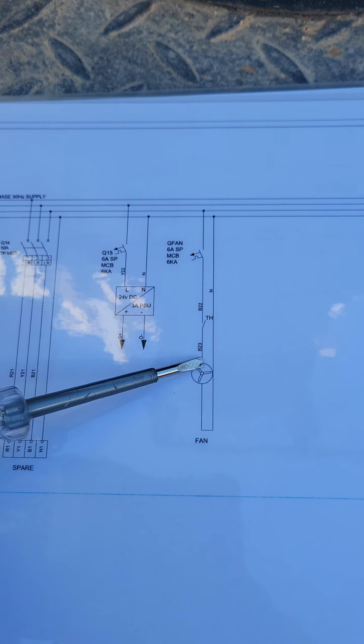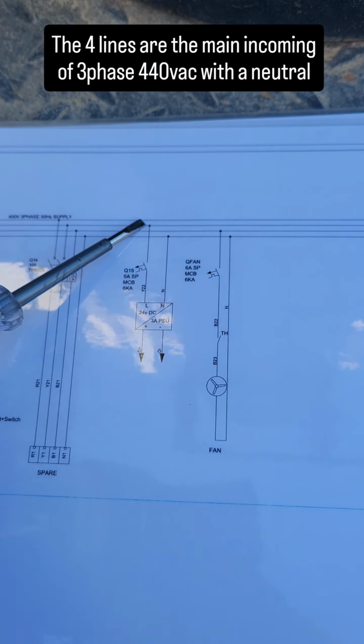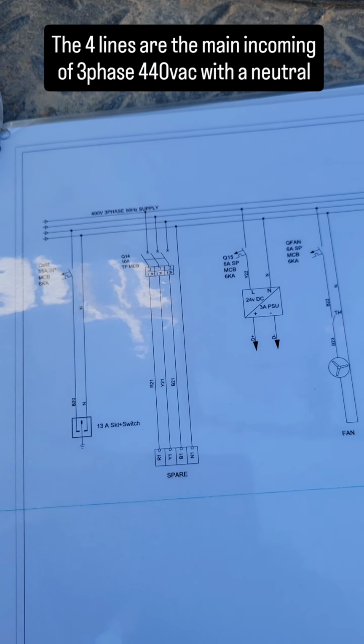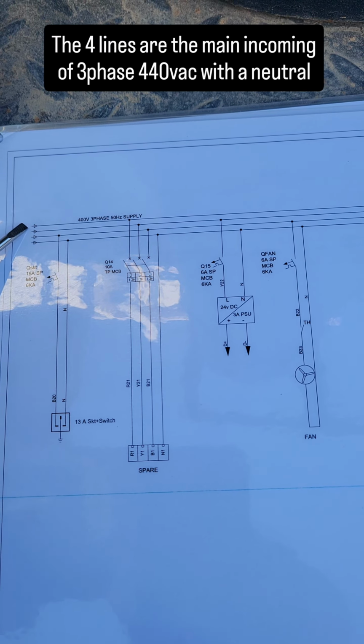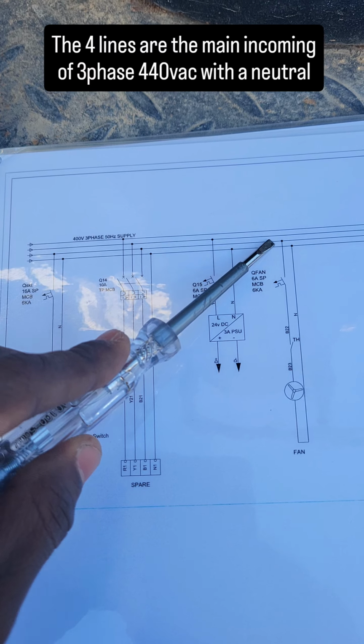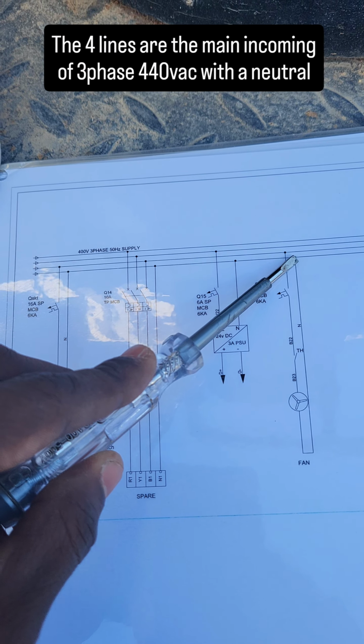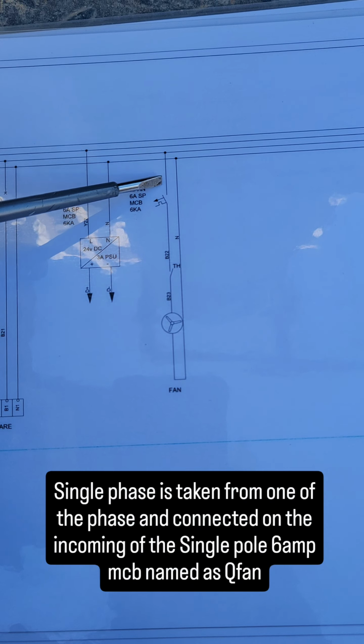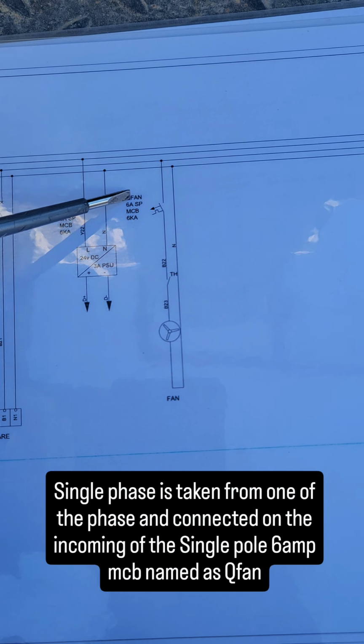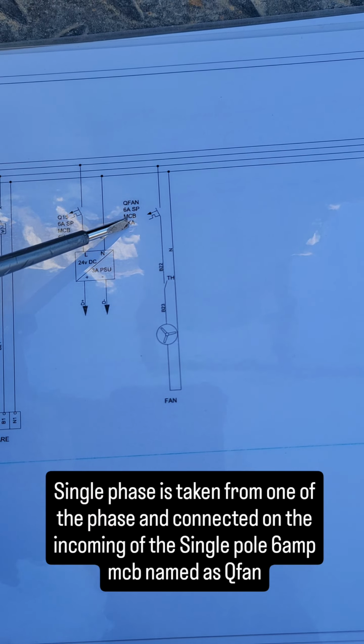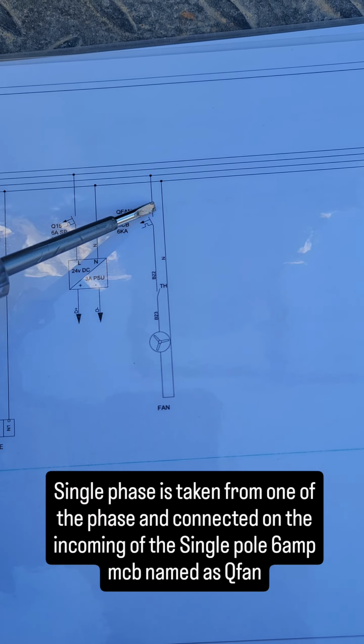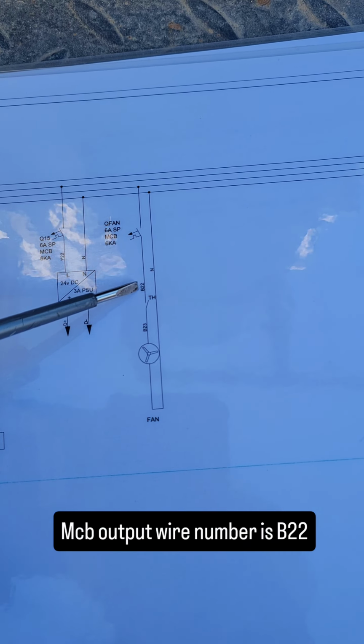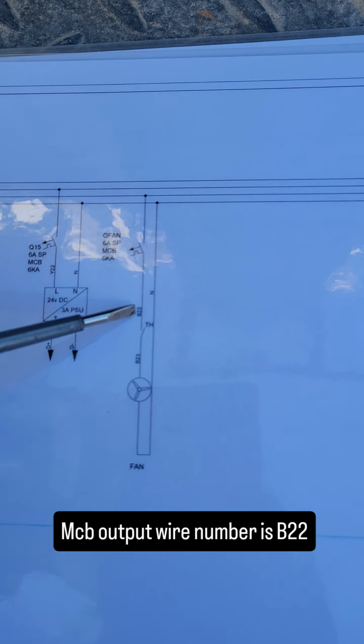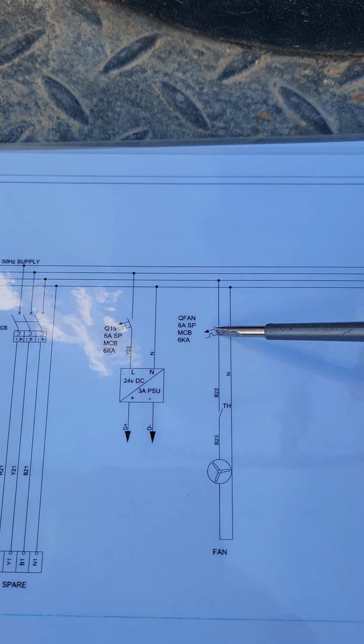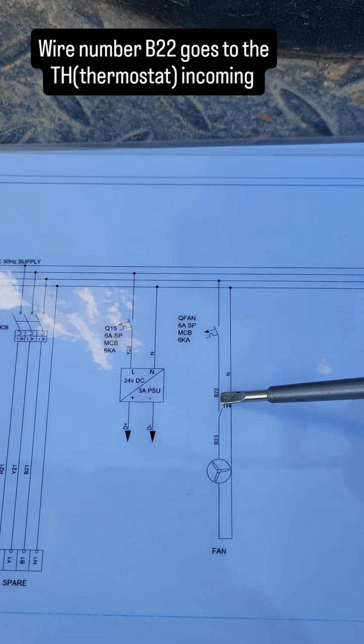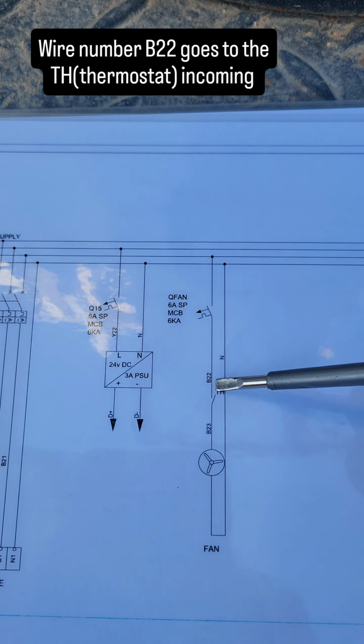Now this is the fan. So the main line is 3-phase and a neutral. You can see that there are 4 lines, out of which 3 lines are phase 1, 2, 3, and the last one is neutral. So they are taking a single phase. The single phase comes to the MCB named Q fan, which is 6 amps and single pole, and from the MCB output the wire number is B22. So the output of the MCB, wire number B22, goes to the input of the TH.